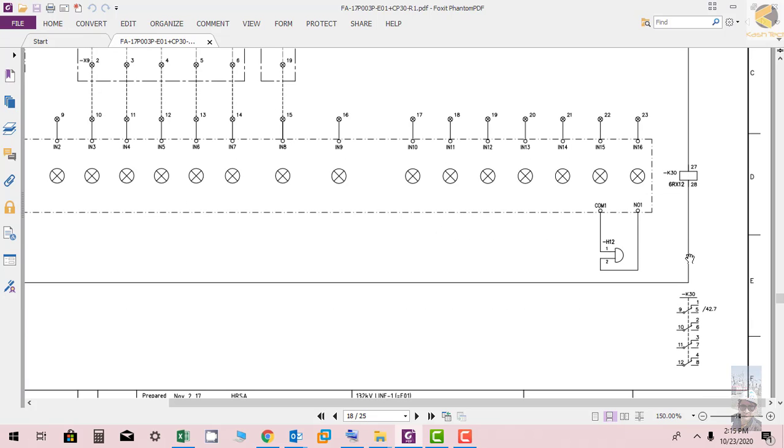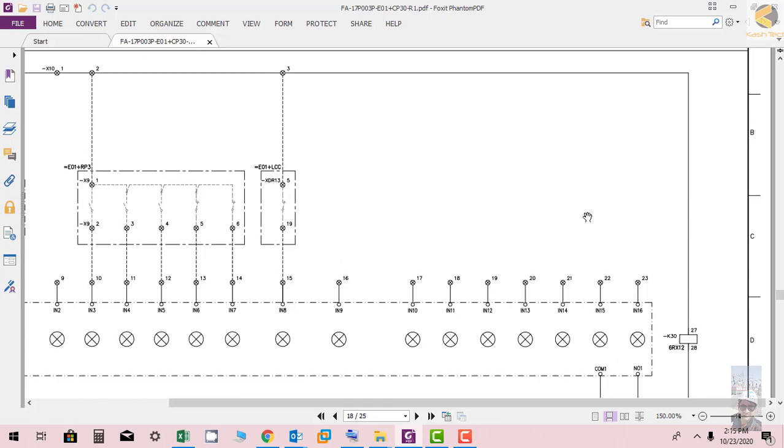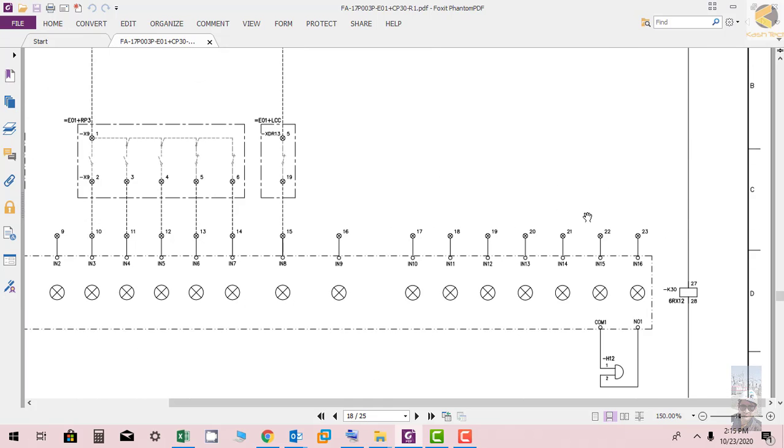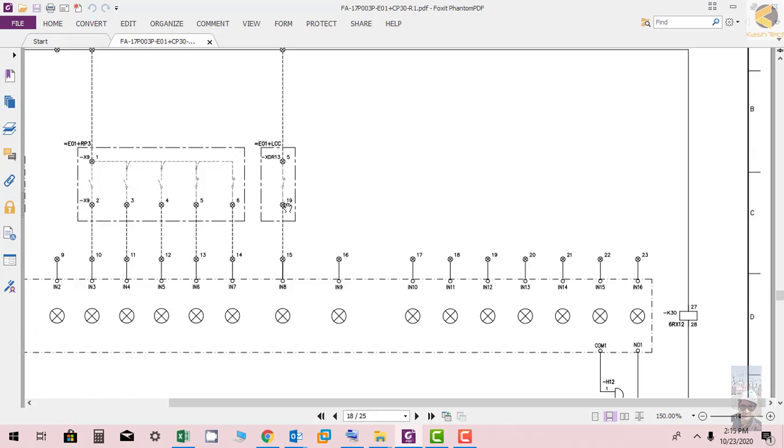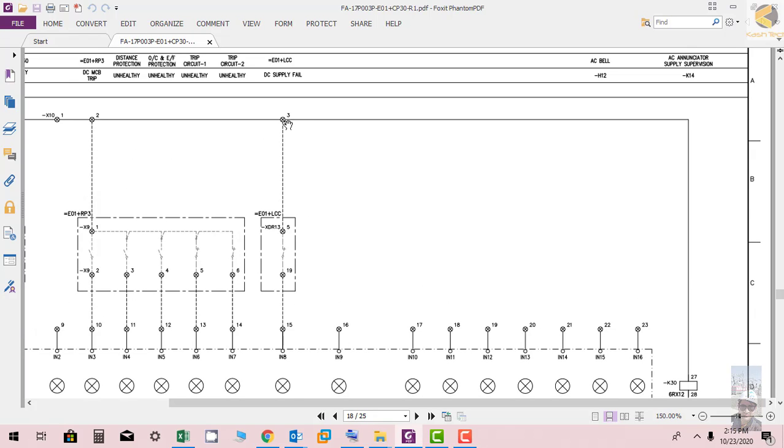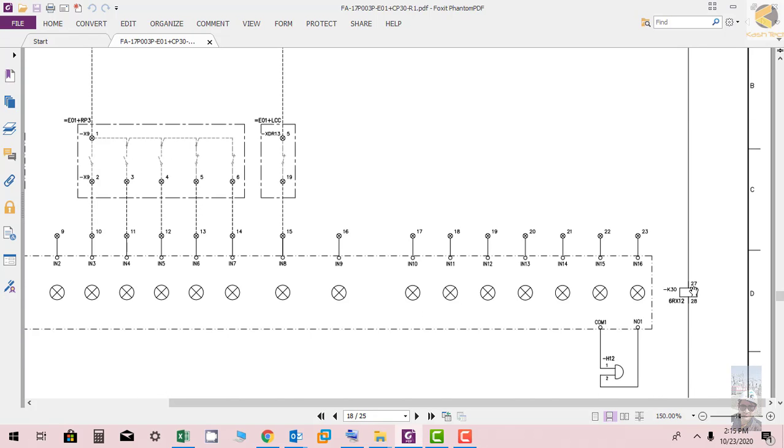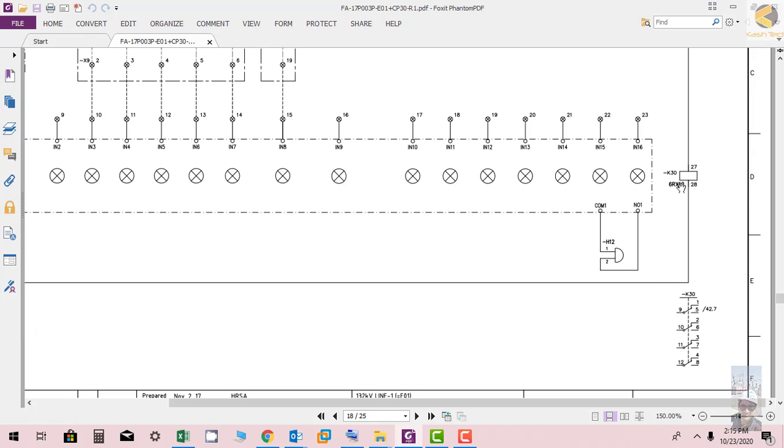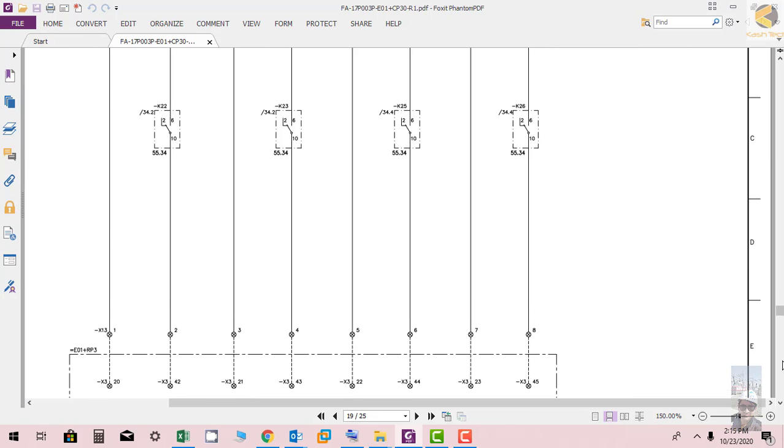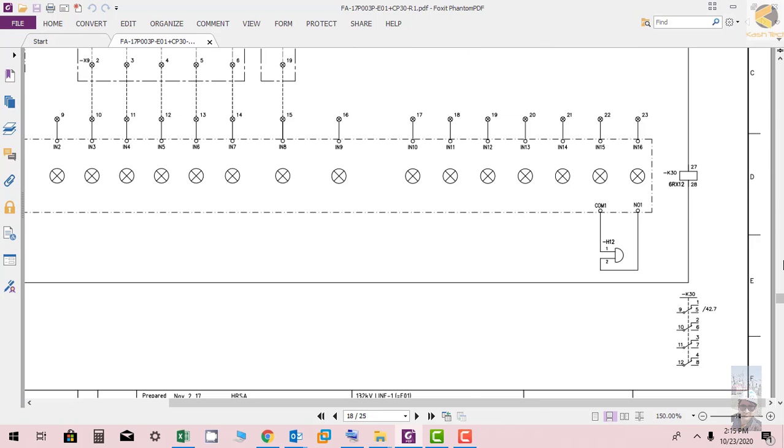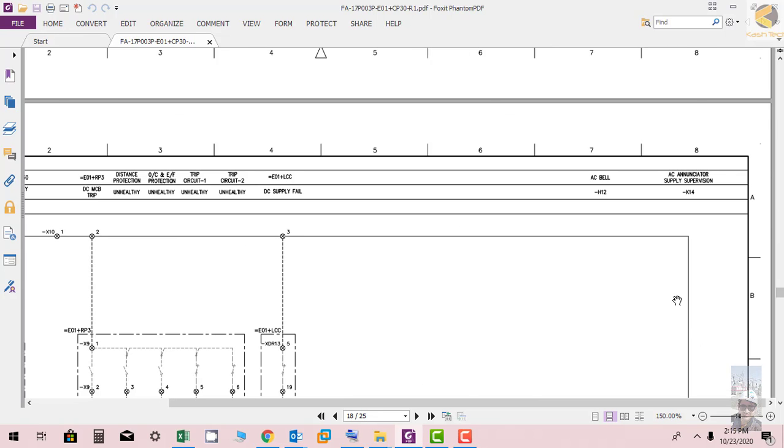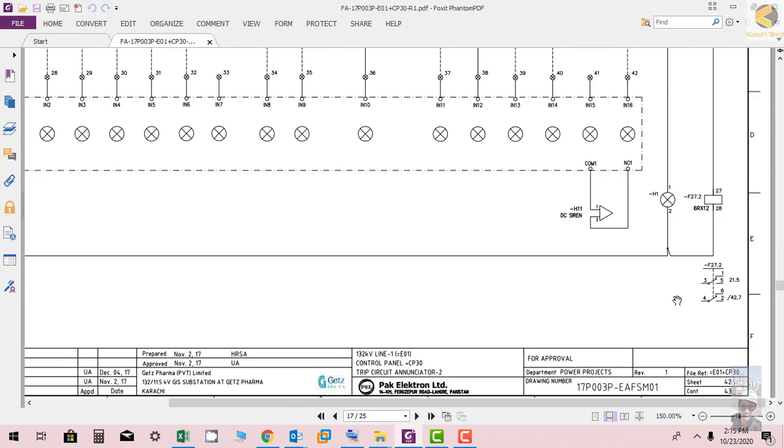If AC supply at the end of the loop is disturbed with any of the wire, for example here from here wire is open, there will be no supply at K30 and the K30 will be switch off or drop off. You can see one contact is used 42.7. So we are at sheet 43, go to 42.7.